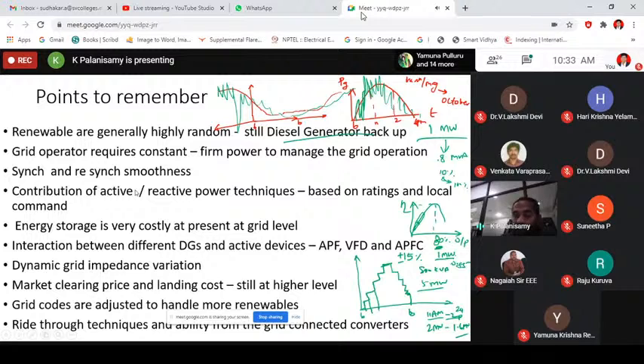So during that time, you are going to connect an inverter in parallel to the grid, right? Like that, there may be n number of inverters connected, synchronous generators connected, and many other loads. So when random numbers of solar PV stations or diesel generators or loads come and go out of the station, what is happening? Indirectly, the grid impedance is highly dynamic or highly varying. The proper operation of, let's say, a shunt active filter, a variable frequency drive, active power factor correction devices, or other solar inverters needs almost a constant or small bandwidth of grid impedance.